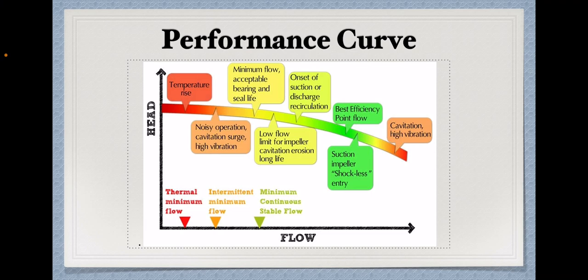Initially, there is an onset of suction or discharge recirculation which could lead to impeller cavitation and on further reduction of the flow. There is a possibility of reduction in bearing and seal life.